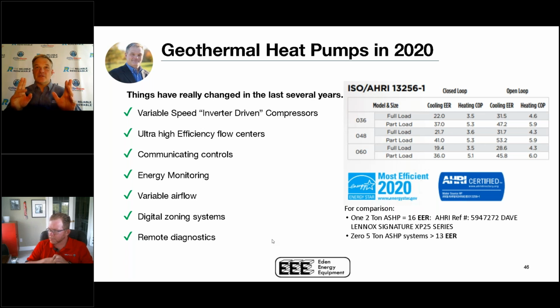Now, let's put that EER in perspective. That's for an air source heat pump at 95 degrees. Today in Ontario, that's today's weather, there is one air source heat pump that achieves 16 EER. And it's a little bitty 2-ton unit at 95 degrees Fahrenheit, period. There's one listed in the world that qualifies. There are no 5-ton air source heat pumps whatsoever above 13 EER at your current temperature in Ontario today. So not above 13. Most are closer to 10 or 11.